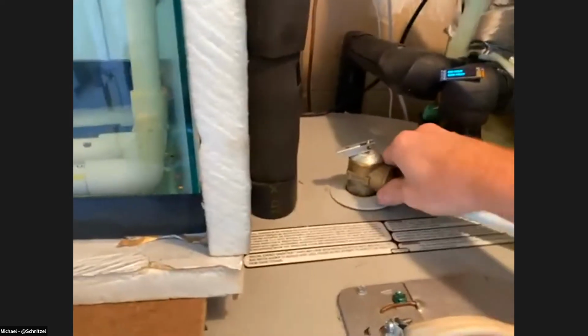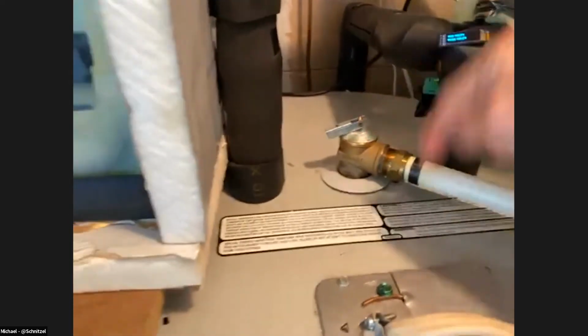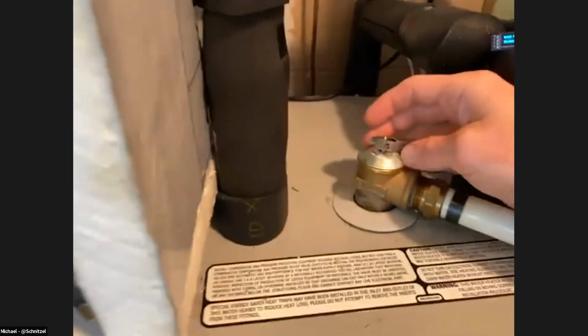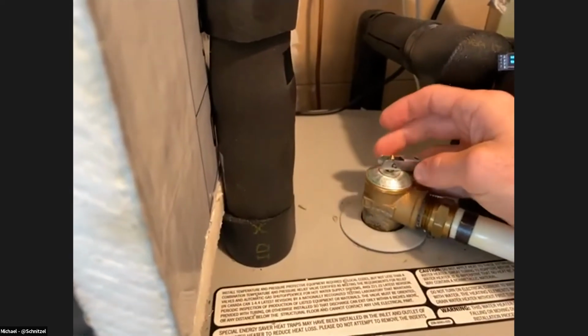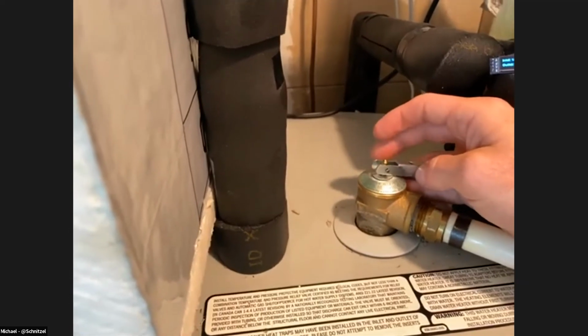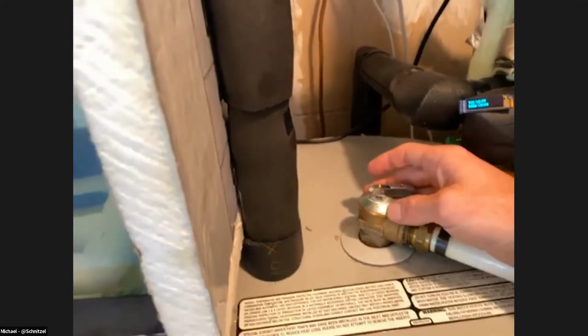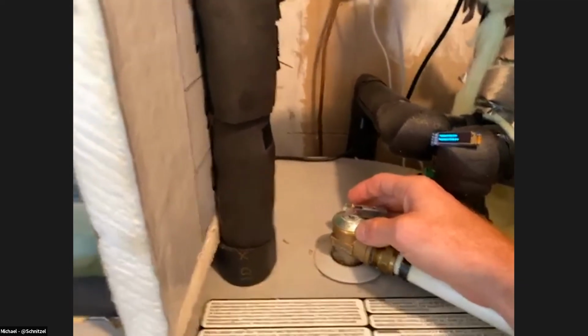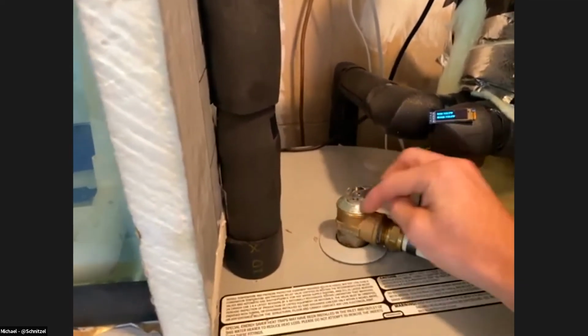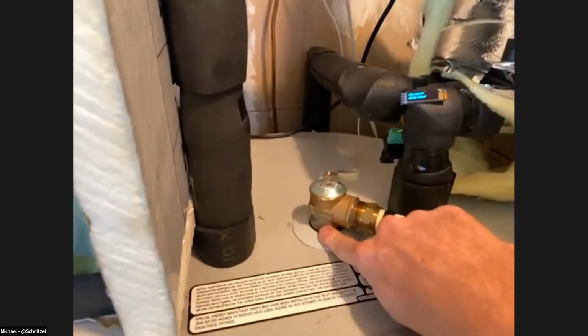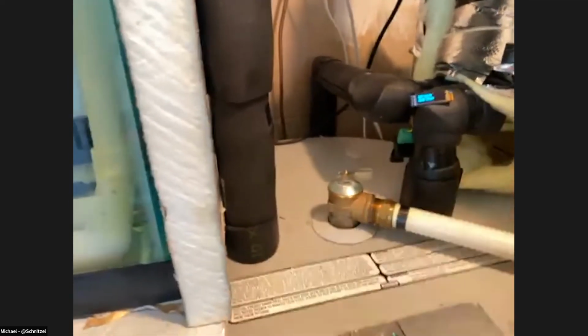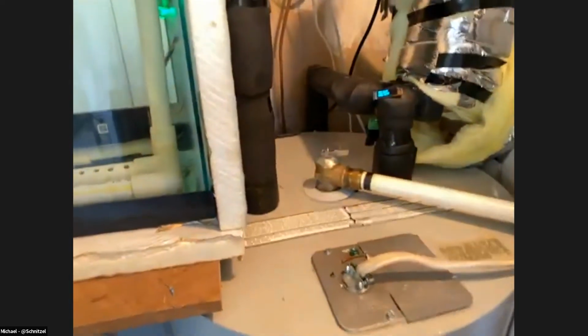There's also this pipe, which some people might want to know about. It's just an exhaust, and there's a safety valve here. If the water inside got hotter than roughly 210 Fahrenheit, just below boiling, and 150 PSI, it would open up. So that's a safety valve for if the water gets too hot. If it opens, it doesn't go anywhere in particular, it just drains at the bottom. It's purely a safety feature.